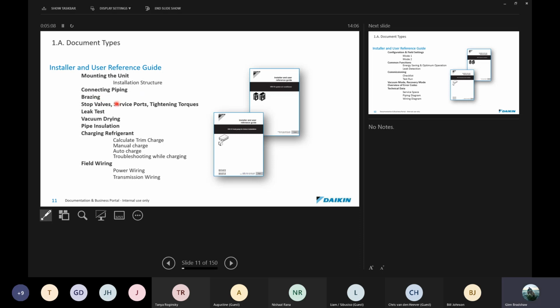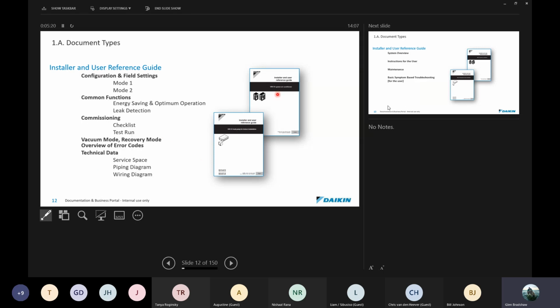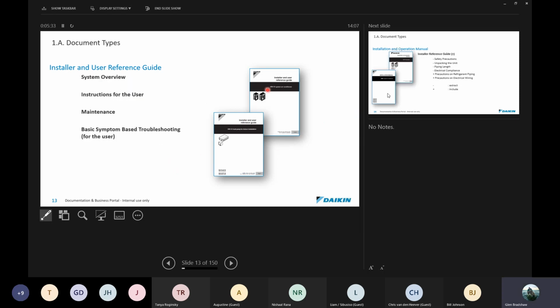Right, and that's everything from brazing, the stop valve service ports, the tightening torques, leak test, vacuum drying, pipe insulation, refrigerant charging, field wiring, and right the way through to the test run, and even some basic fault finding should you have any issues on site. Okay, all right. That's the second type of documentation.